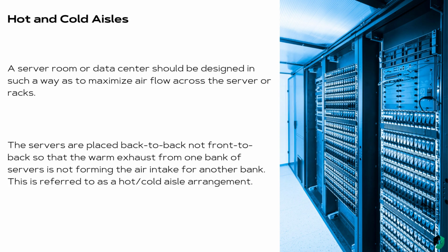And then hot and cold aisles. A server room or a data center should be designed in such a way as to maximize airflow across the server or the racks. Now, there is a very important style of actually placing your servers in a server room. See, the servers are placed back to back, not front to back. And the reason is because we don't want the warm exhaust from one bank of servers forming the air intake for another bank.